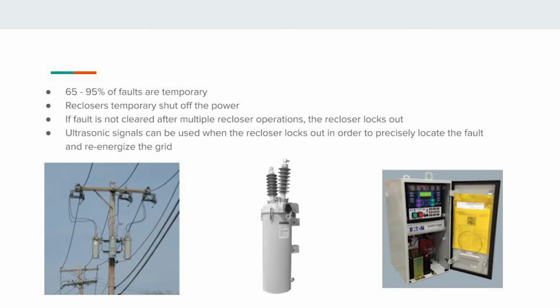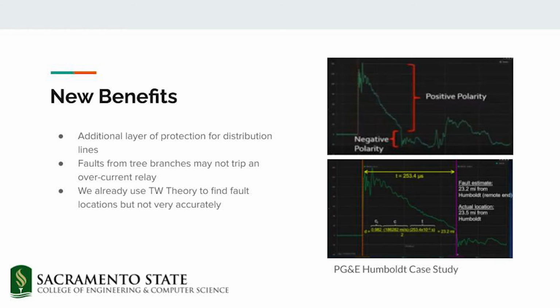With the existing infrastructure of reclosers, an ultrasonic sensor can be added to the control module. The ultrasonic sensor will send a signal every time the recloser opens in order to accurately locate the fault on the de-energized line. This new age fault detection scheme can add an extra layer of protection to what we already have in place. Current protection schemes are designed to stop a fault from happening after it has already happened. With this, we are being proactive and setting up a system to detect a fault while it's happening.